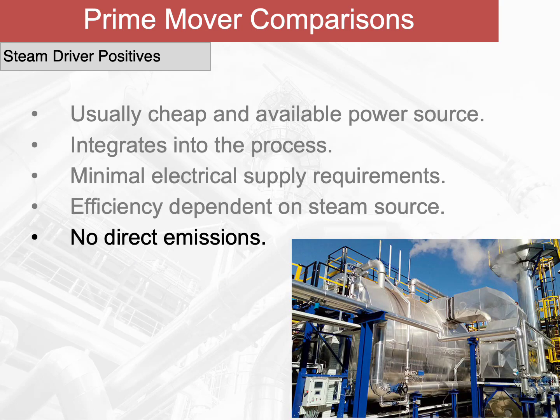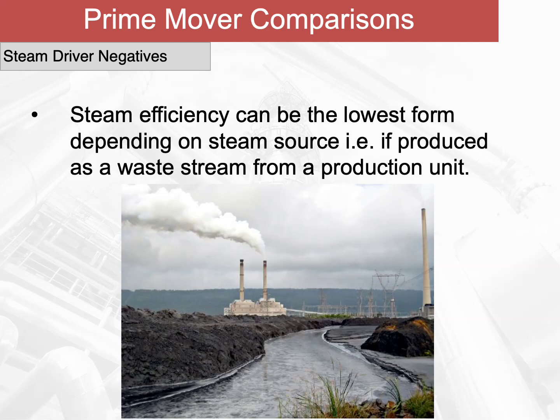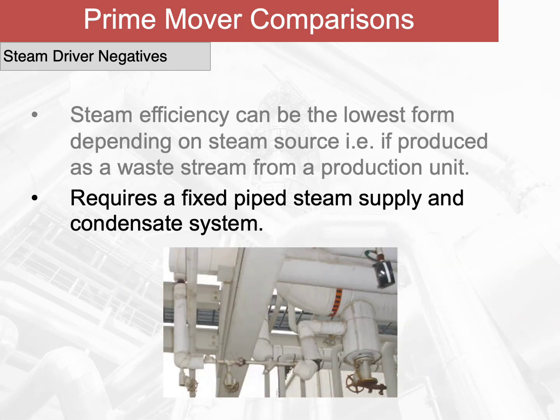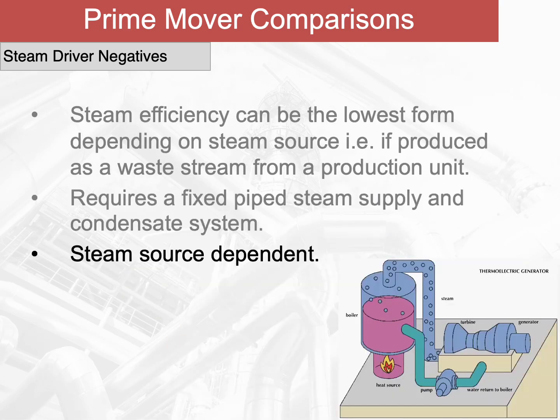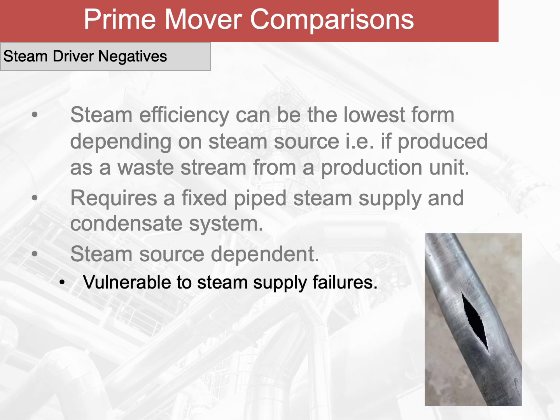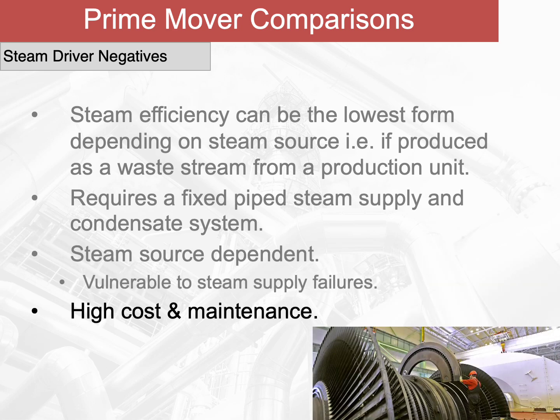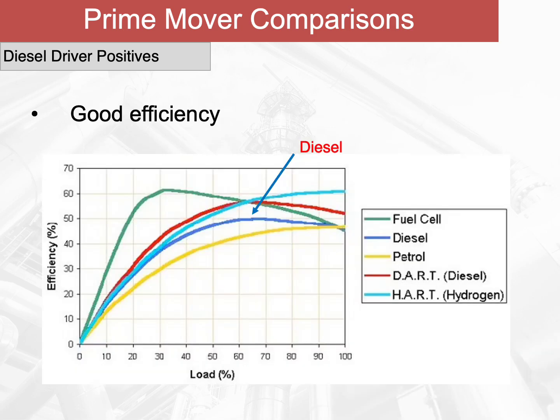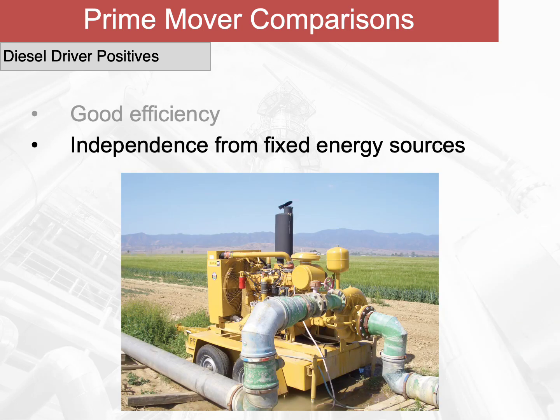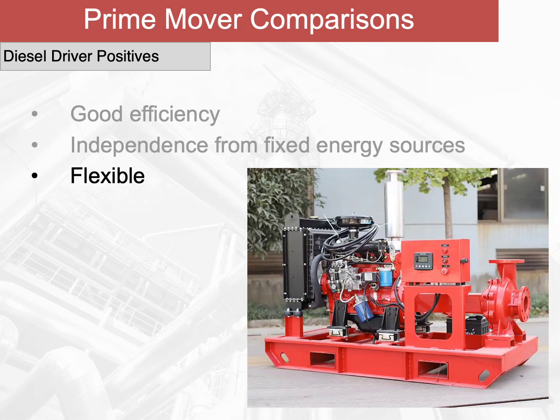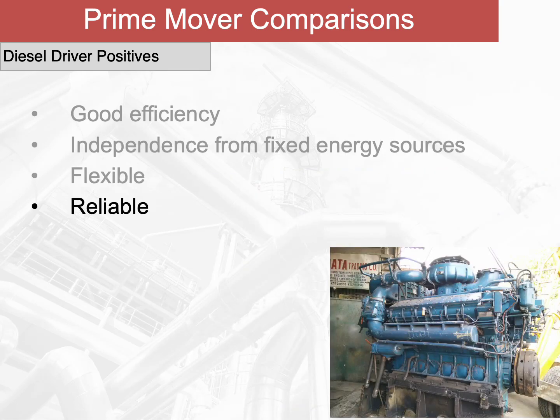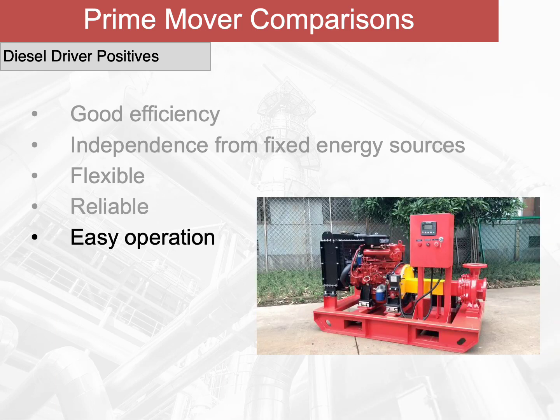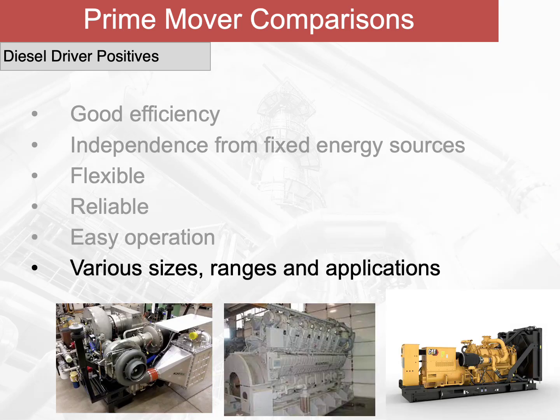No direct emissions. Steam driver negatives. Steam efficiency can be the lowest form, depending on steam source, as an example, if produced as a waste stream from a production unit. Requires a fixed piped steam supply and condensate system. Steam source dependent. Vulnerable to steam supply failures. High cost and maintenance. Diesel driver positives: good efficiency. Independence from fixed energy sources. Flexible. Reliable. Easy operation. Various sizes, ranges and applications.